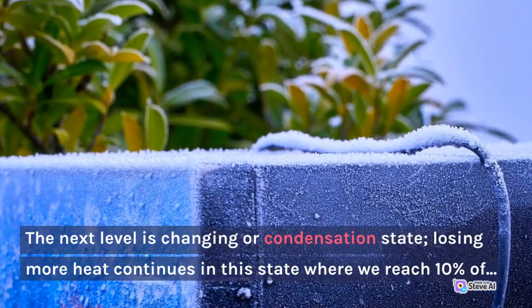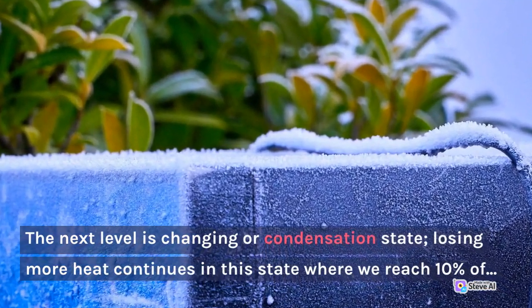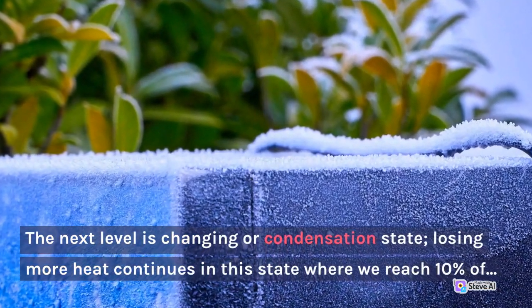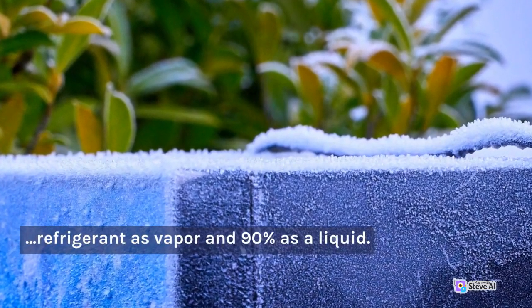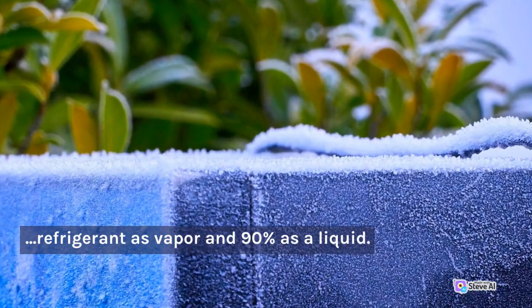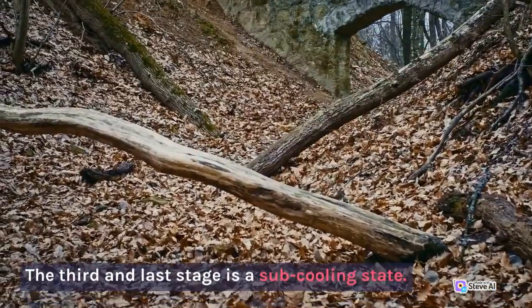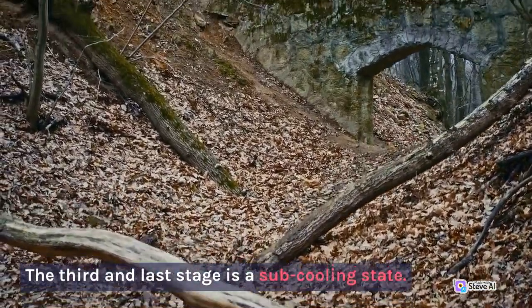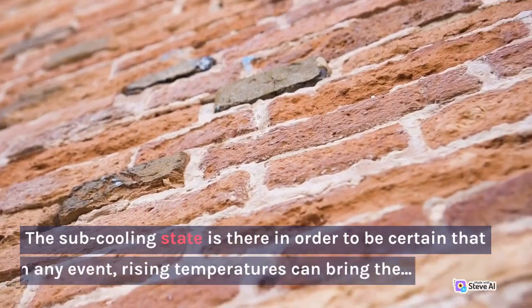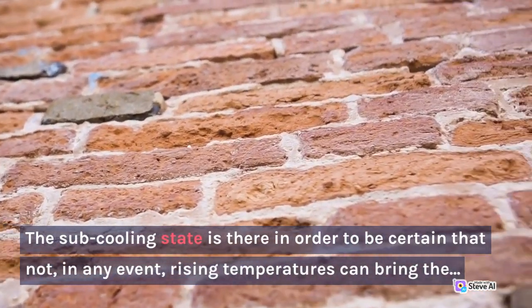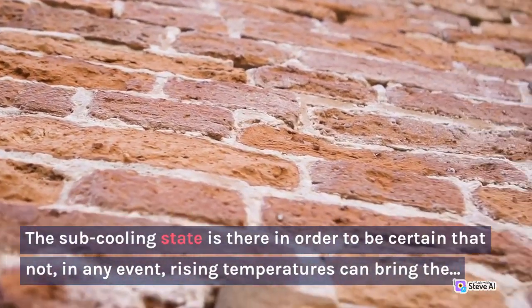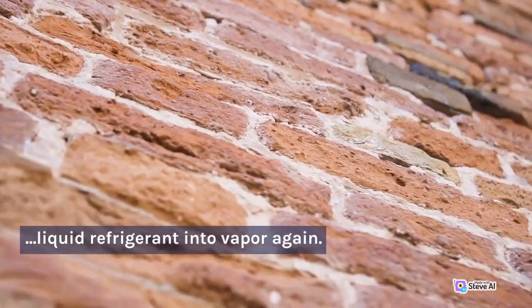The next level is the changing or condensation state. Losing more heat continues in this state where we reach 10% of refrigerant as vapor and 90% as a liquid. The third and last stage is the subcooling state. The subcooling state is there in order to be certain that not even rising temperatures can bring the liquid refrigerant into vapor again.